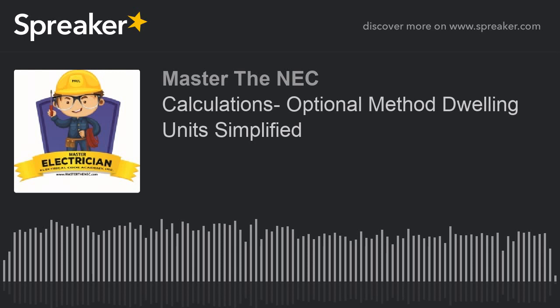Unlike the standard method where I had to go to 220.12 and ended up going to the table, since we know that we're doing dwelling units, because that's what the header, or the charging statement under 220.82 is, dwelling units, then immediately it tells us to use 3 VA per square foot for the general lighting and receptacle use. Okay? We got that. It also reminds us, again, use the outside dimensions for our square footage, and we did that with the standard method, so nothing else changes.